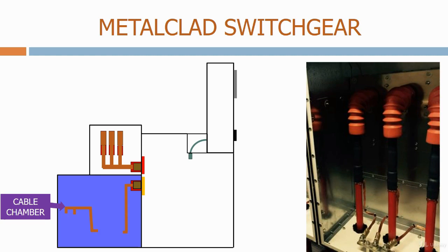Inside the cable chamber, we also have current transformers, so that we can measure the currents on each individual circuit. If we need to measure the voltage, we provide VTs. These can be provided in the cable chamber to measure the voltage for each circuit, and above the busbar chamber to measure the busbar voltage.